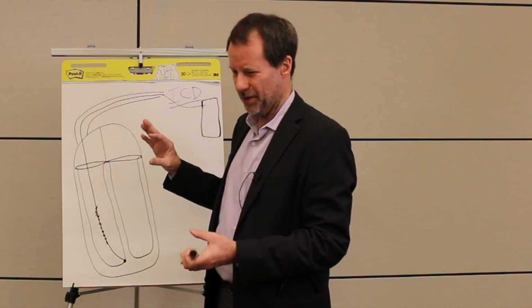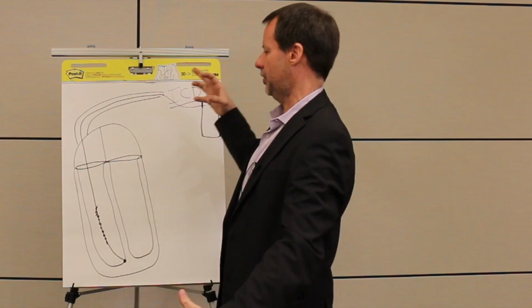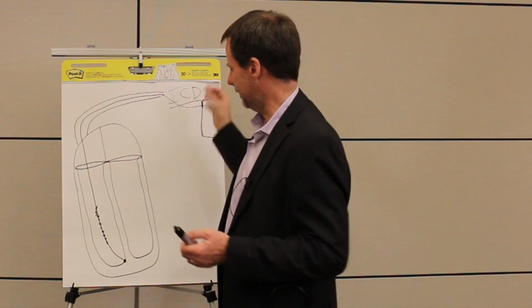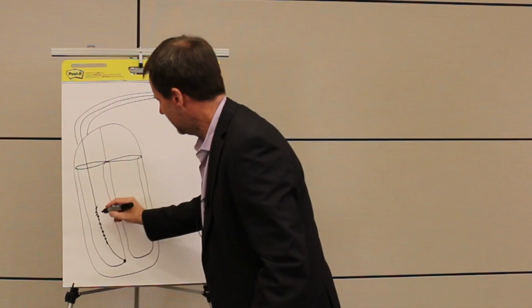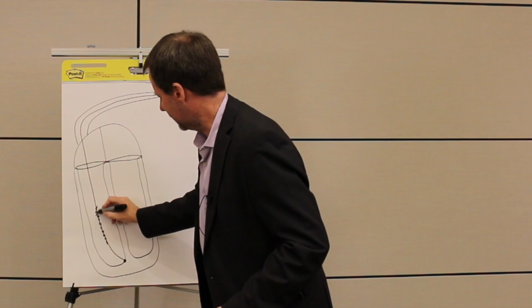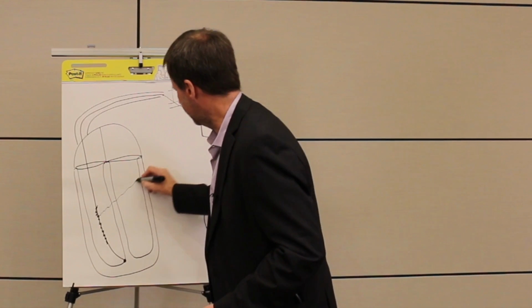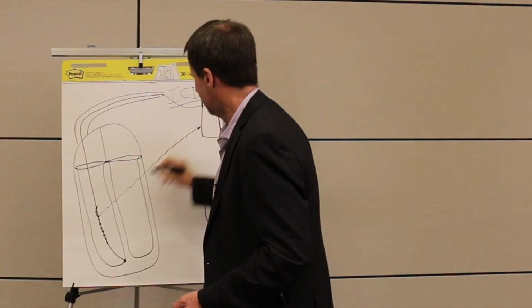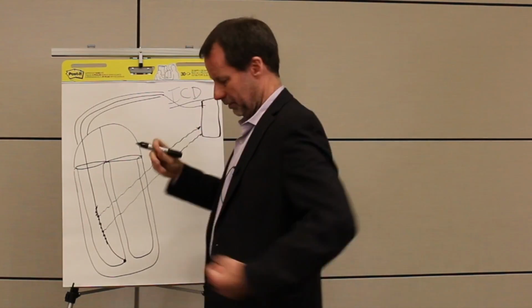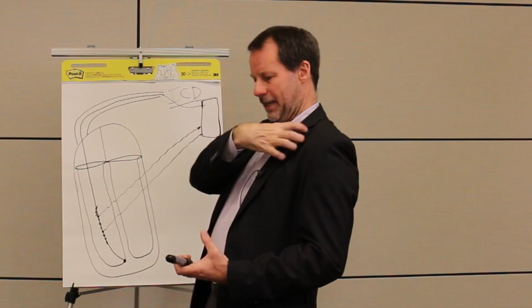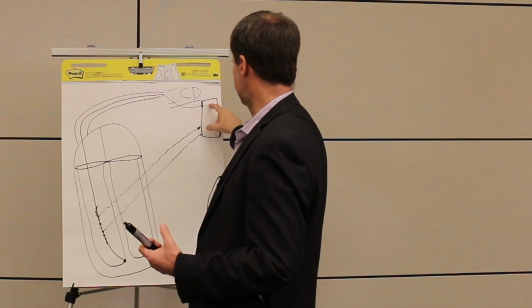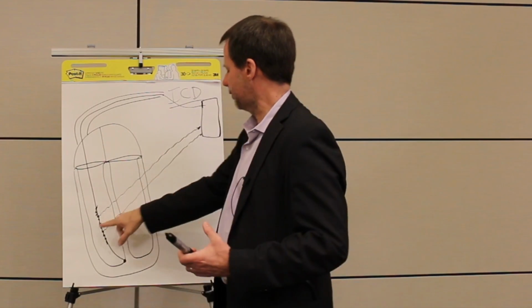Some of these will stop on their own. It'll wait a couple of seconds. If nothing happens, it's going to charge up. And then generally within 10 seconds or less, it'll deliver a shock. And the shock is a very high energy pulse that comes out of this shocking coil and it essentially grounds up here to what we call the can. So just like you have two paddles for shocking someone externally, this is essentially one paddle inside the heart, and then the device itself, which is a metal can up here, serves as the other paddle, and the shock is delivered through the heart up to the can, and that will actually convert the heart back to normal rhythm.